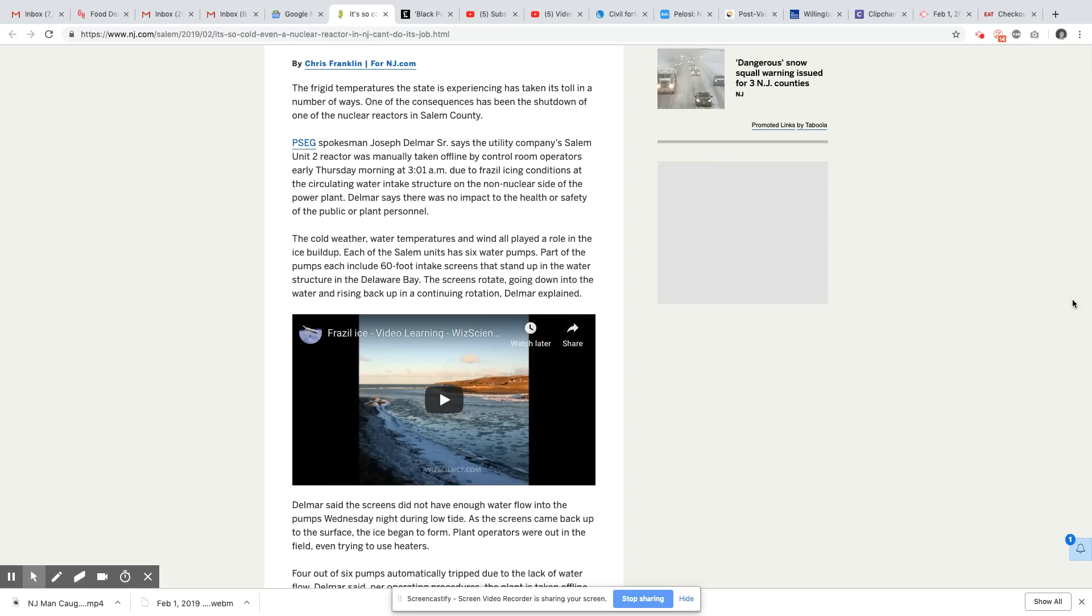One of the consequences has been the shutdown of one of the nuclear reactors in Salem County. PSEG spokesman Joe Delmar Sr. says the utility company's Salem Unit 2 reactor was manually taken offline by control room operators early Thursday morning at 3:01 a.m. due to frazil icing condition at the circulating water intake structure on the non-nuclear side of the power plant.